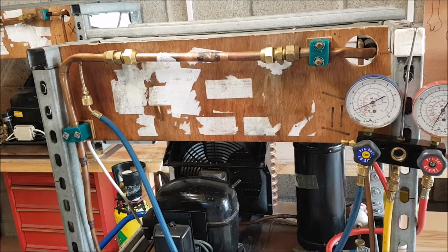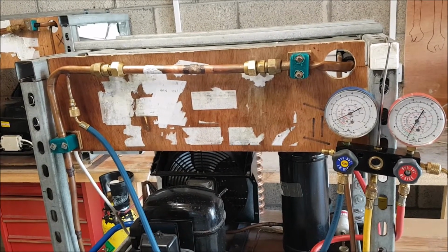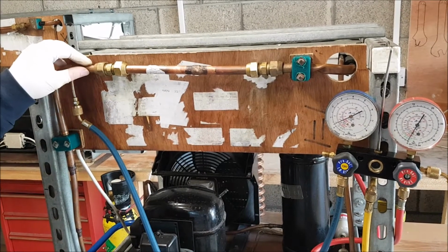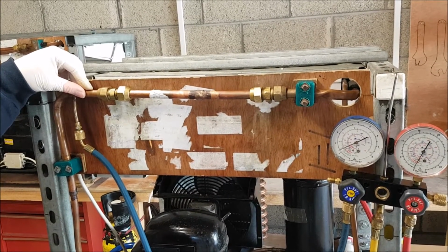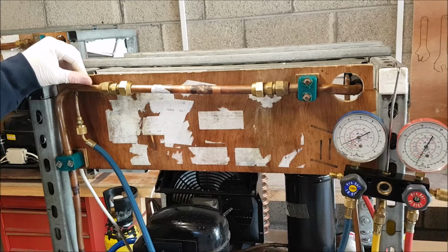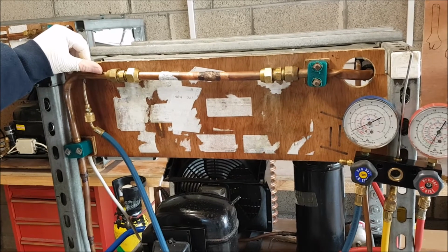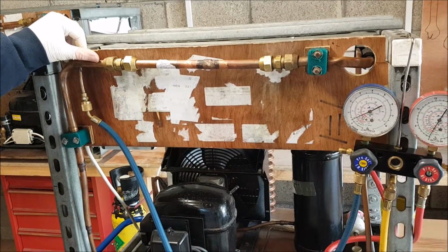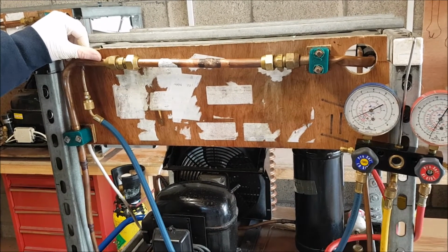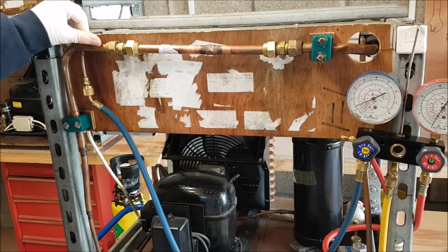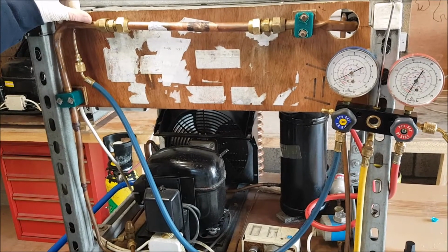So we've recovered our refrigerant, we've carried out our repairs. The next thing we must do under the F-gas regulations is make sure that this system is leak tight. In other words, once we charge this up with refrigerant, there is no possible way of refrigerant escaping to the atmosphere. The only way to satisfy yourself that a system is leak tight is by putting pressure into it. We cannot put refrigerant into it if we are unsure whether or not the system is leak tight. So you cannot add refrigerant to a refrigeration system, heat pump or otherwise, knowing that there's a leak in it. That's against the law.